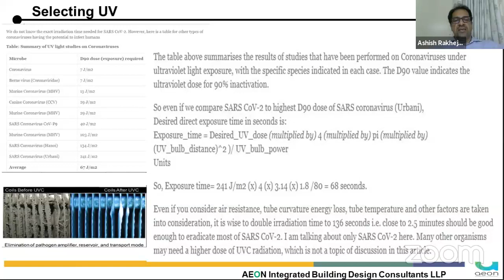There are a lot of solutions being implemented in healthcare which say you just pass the air through UV and your problems are solved - that may not be the case. UV can be used for disinfecting surfaces, but if you want to clean the air, we need a higher air change rate and more time of contact. And to get that more time of contact is not easy in an existing system where air is traveling in the duct for only a few seconds before being discharged.